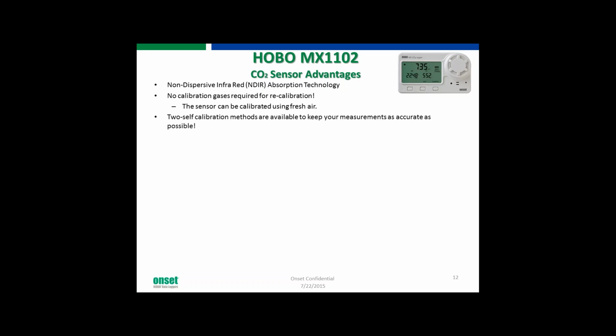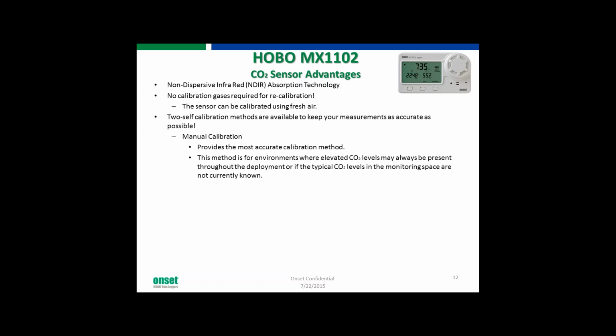We have 2 self-calibration methods that are enabled by default when you buy the logger or when you launch it. Manual calibration, we consider this the most accurate calibration method. We recommend this method for environments where elevated CO2 levels may always be present throughout the deployment, or if you're monitoring a space where you don't know what the CO2 levels are. Typically, that's why you do monitor CO2, because you don't know what those levels are.